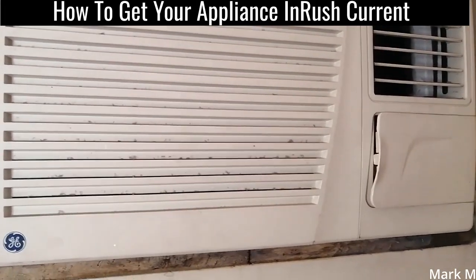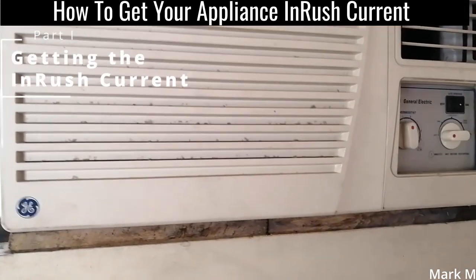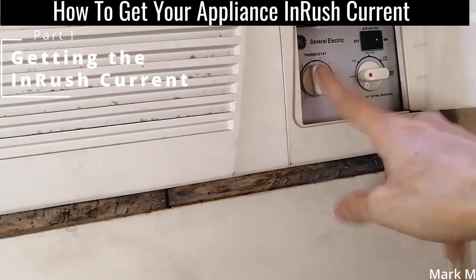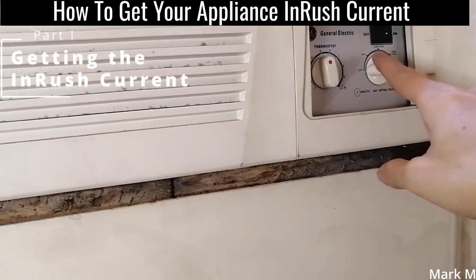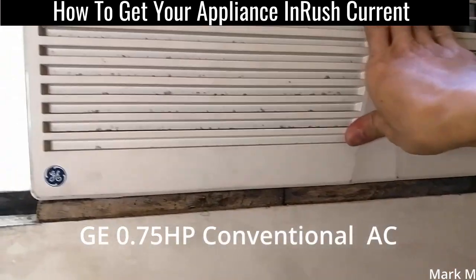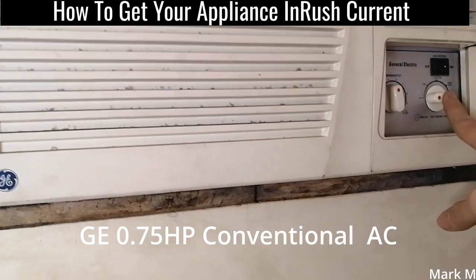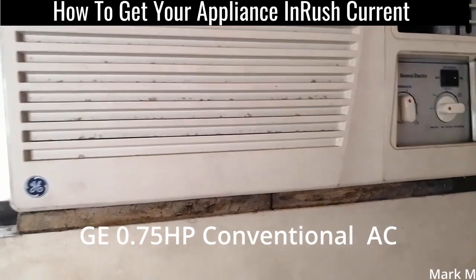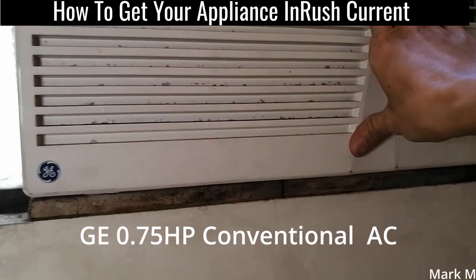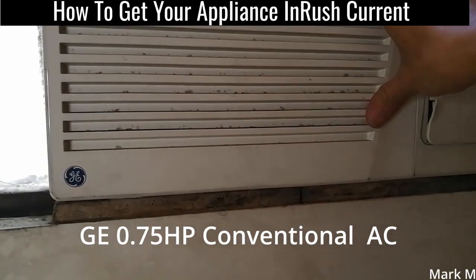It's back to work and we're going to power up this GE 0.75 horsepower air conditioner. The settings are: off, low cool, high cool, and turbo. We're going to check how big the inrush current is in low, high, and turbo modes, to see what specific inverter can handle this unit. This is an old-type compressor-type, not an inverter type.